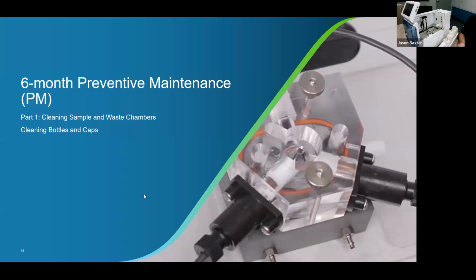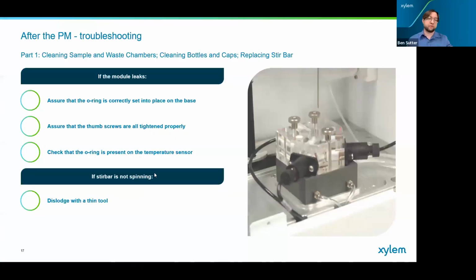Thanks, Jason. That was section 1. Now, a lot of times, right after we do a PM, in my experience as a tech support, I've heard a lot of different things that happen directly after. So as Jason goes through this, I'm going to talk about a few things that you may notice. As that occurs, you can kind of nip them in the bud by just knowing exactly what you're looking for. So here are some things that happen after the preventive maintenance that you may want to look for. If the module leaks after you put it all together, you want to make sure that your O-ring is correctly set into place on the base.